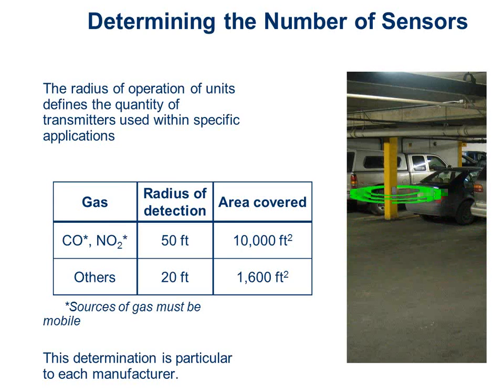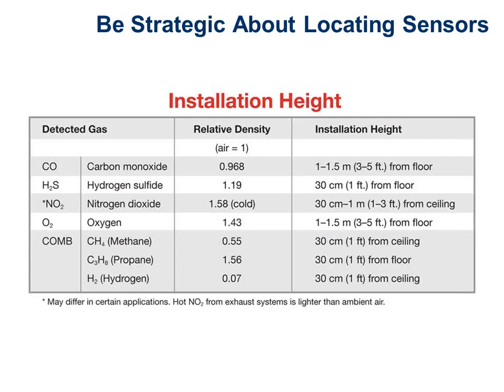All right, here gives you some relative densities of some of these things. So you can see carbon monoxide is 0.968 relative to air, which is 1.0, right? So carbon monoxide, I want to measure in the breathing zone, you know, that 3, 4, 5, 6 feet above the floor type of thing. If I look at oxygen, relatively speaking, it is similar to air as well. If I look at some of the other ones, like nitrogen dioxide, when it's cold, it is heavier, right? So I want to measure that.